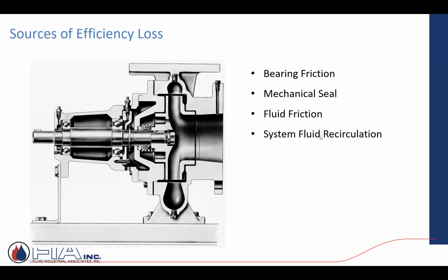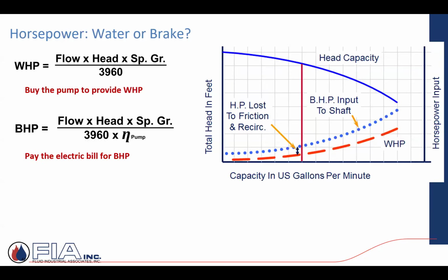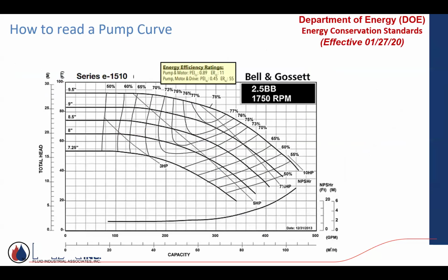As that impeller's adding that velocity and that water's churning in that volute, a high percentage of it discharges out, but a little bit recircs. All of those add up to, and this is a deep dive into the engineering of how a pump is built, just behind the scenes. You're not going to spend all your time on it, but go back real quickly to that pump curve.